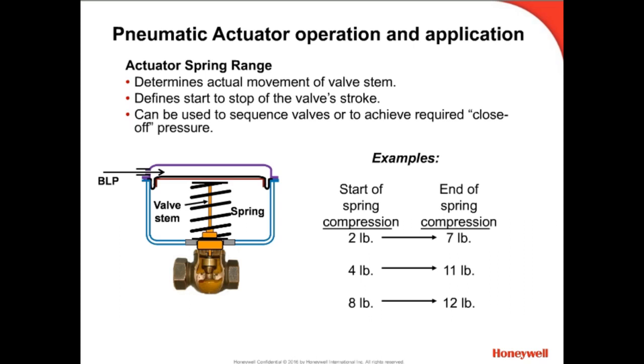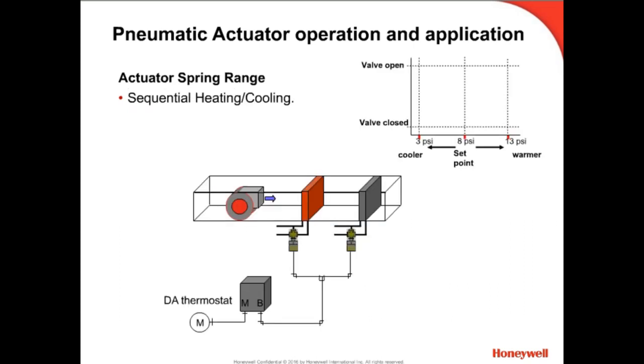The spring range is often applied to achieve tight close-off against water or steam flow. The air pressure or spring pressure at one end of the stroke or the other will hold a normally open or normally closed valve tightly closed. Spring ranges are also needed for valve sequencing to meet specific control strategies.